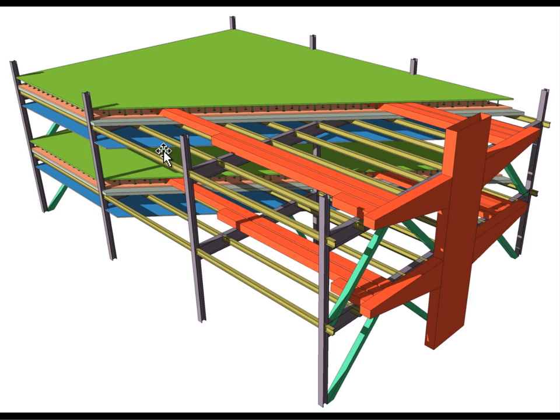A second reason for continuous plenum volumes in both floor and ceiling is building flexibility. The client wanted the ability to rearrange interior partitions at any time and still get air to any new space. Plenum volume provides that power — if you're occupying floor area you have plenum supply at the bottom and plenum return above the ceiling, so there's no need to rearrange ductwork either under the floor or above the ceiling.